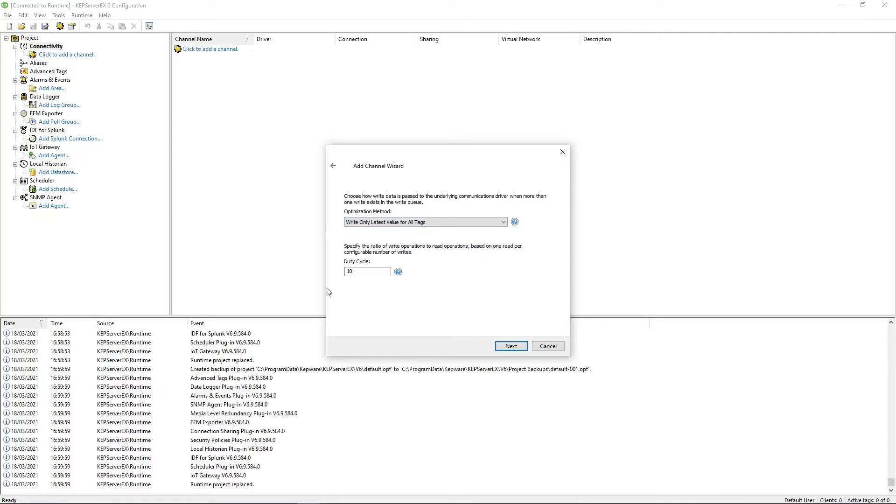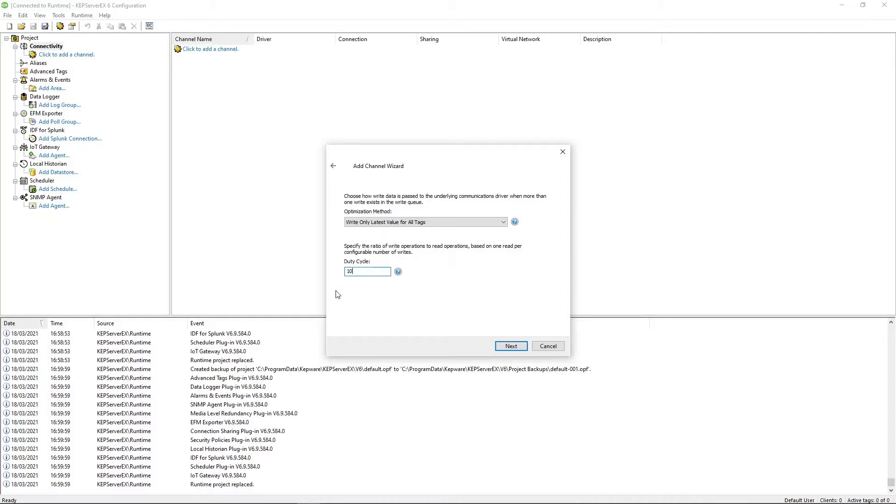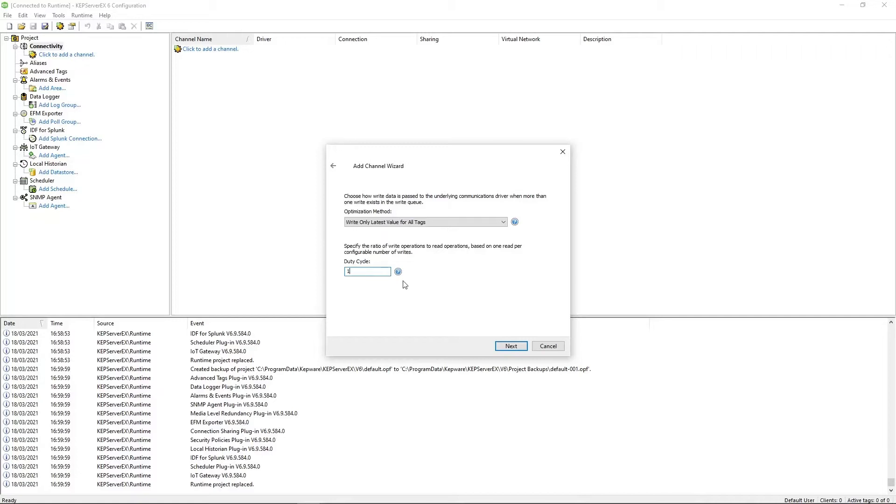And then this other option here, it specifies the ratio of reads to writes from KEPWAR to the PLC. So that would be one read for every 10 writes as it's currently set by default. And this would be the case if you have a system where you need to be in constant communication writing out to the PLC, but you only need to read from it every now and then. In this case, this is perfect. In fact, you keep your 10 writes to every read and it makes sure all the writes go out on time. But in some cases, this isn't really necessary and you have a more balanced read-write cycle, in which case you could drop that down to maybe one write to one read or five writes to one read. But I'll just leave that the default for this. I'm going to click next.